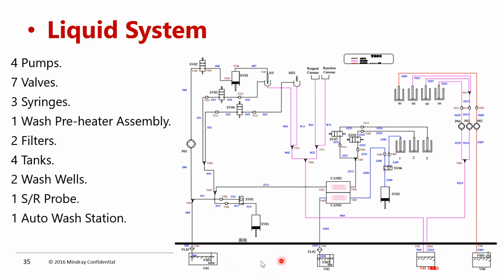In the first slide we saw the instrument; behind it we have connections, right? 2 are input lines, 2 are output lines. Tank number 1 is deionized water. Tank number 2 is detergent. We have to prepare manually a 1:10 dilution of CD80: 1 liter of CD80 diluted with 10 parts of water, and connect it here. So we'll explain how the instrument works.